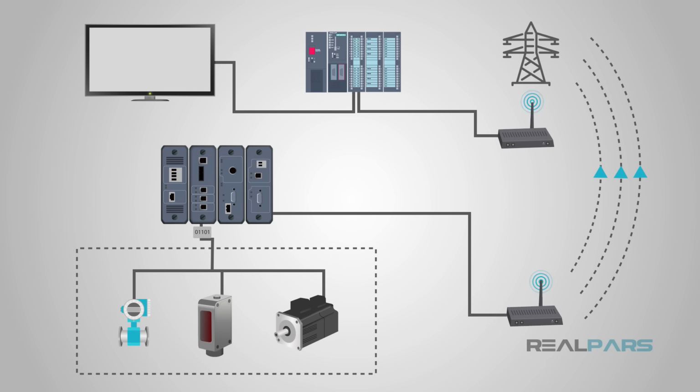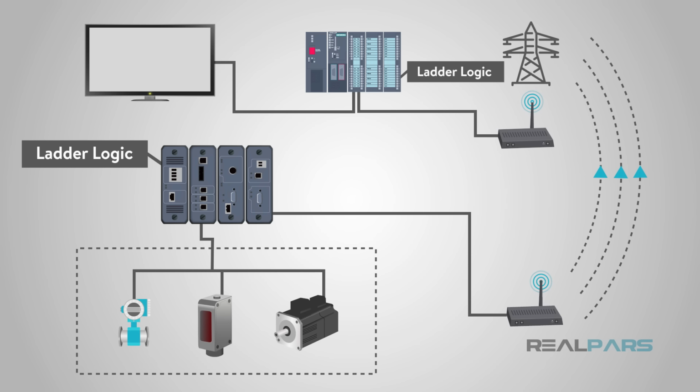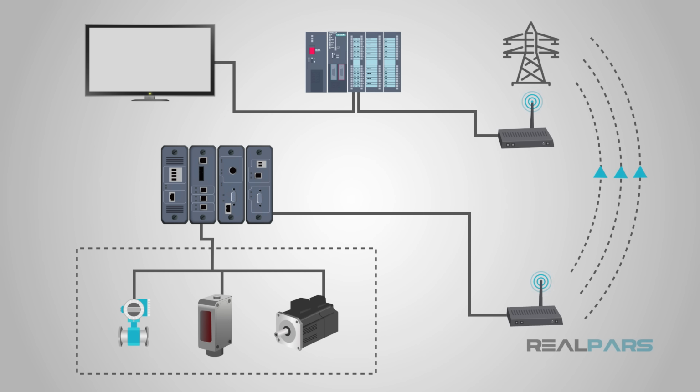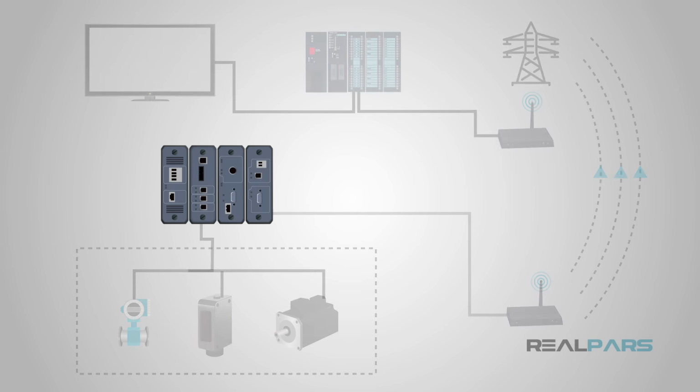Some RTUs may be programmed with languages such as BASIC, Visual Basic, and C#. Of course, these languages require a special skill set just as the PLCs do. Some RTUs are even programmed in the same languages that PLCs are programmed with, such as ladder logic and structured text. A definite advantage is in the environmental tolerances of an RTU.